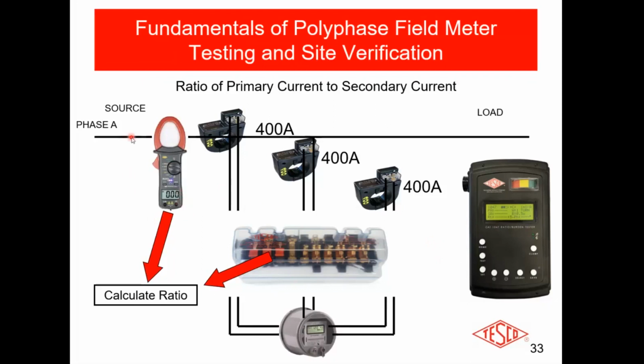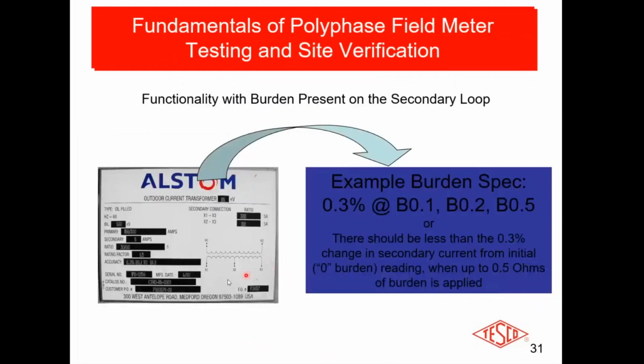And you're simply checking the primary versus the secondary. And you can do that: you have to access the primary and you can check the secondary right from your test switch, and you can calculate your ratio. Now, one of the things, I don't know if you noticed or not, but on this faceplate there were two different ways in which you could hook this particular transformer up. X1 to X3, X2 to X3.